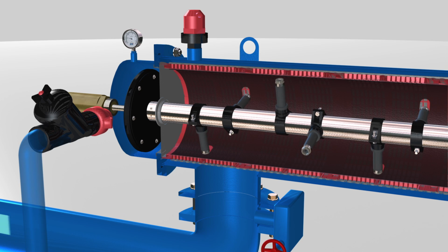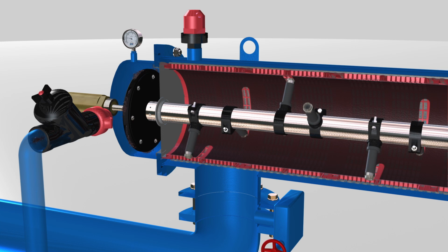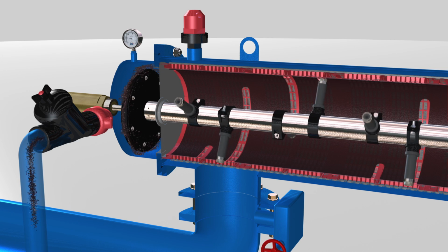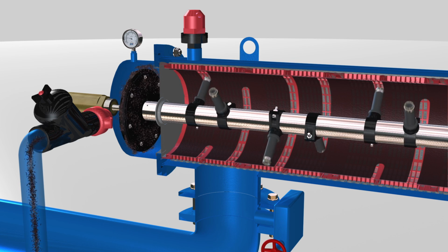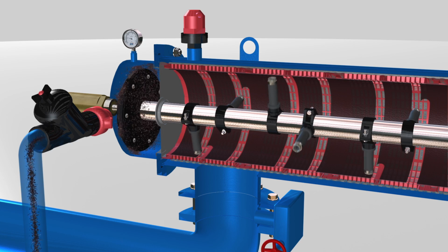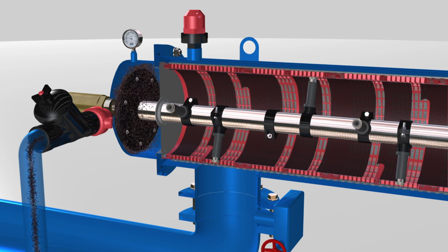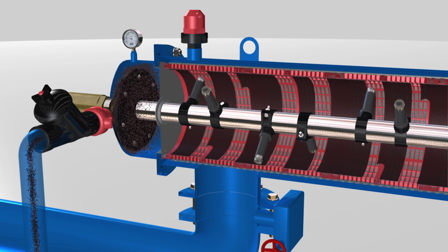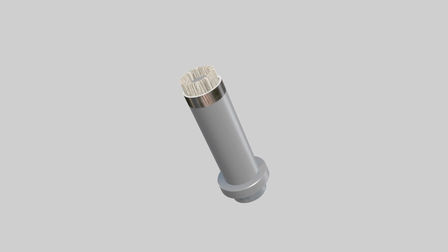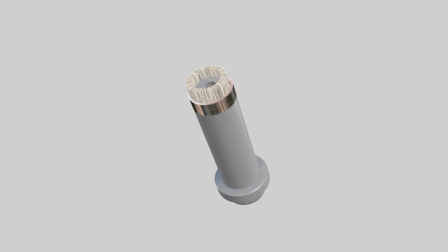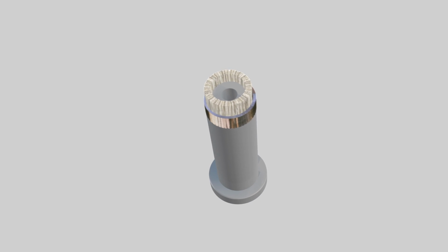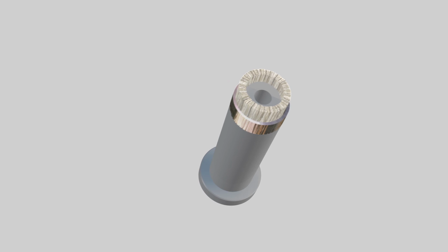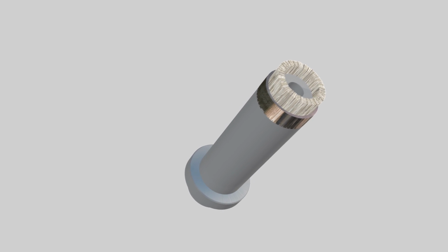Scanner movement enables the nozzles to touch the filtration surface, leaving the cartridge completely clean at the end of the backwash cycle, which lasts 25 seconds. The STF patented nozzle enables a significant saving in the amount of water used in filter backwashing and ensures 100% effective cleaning.